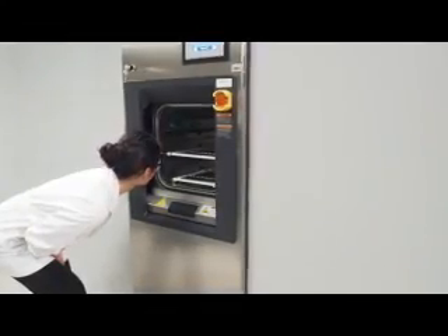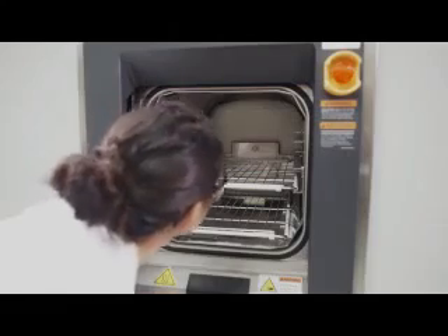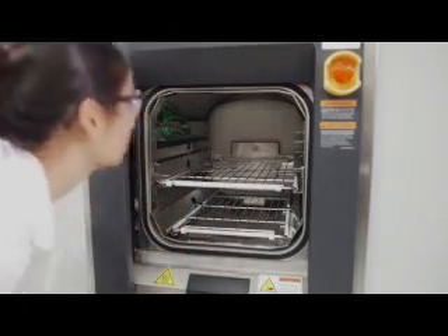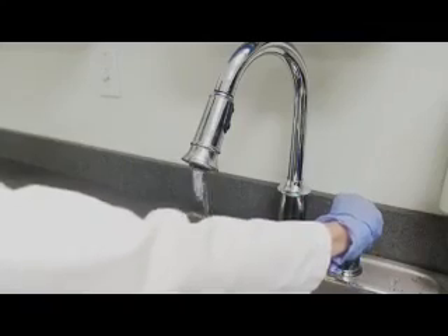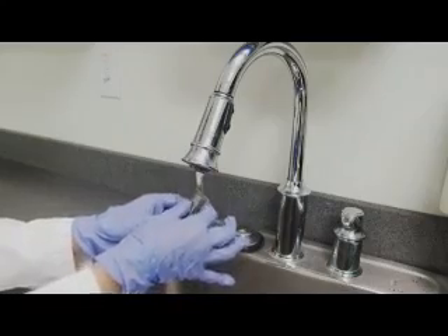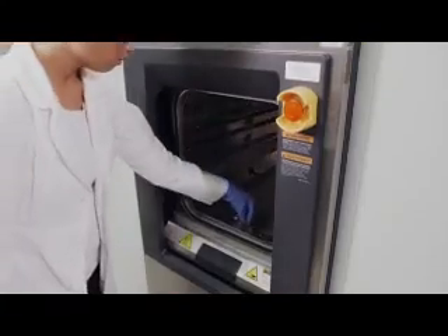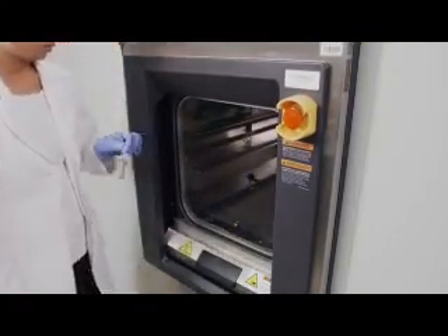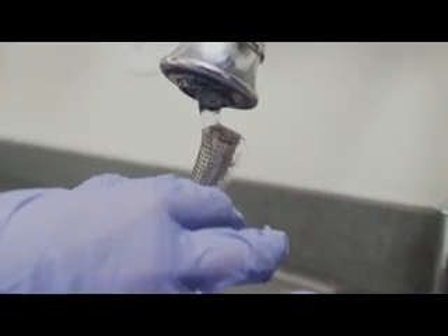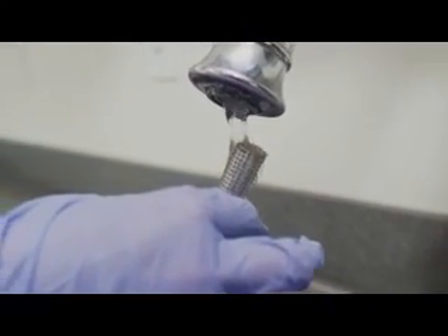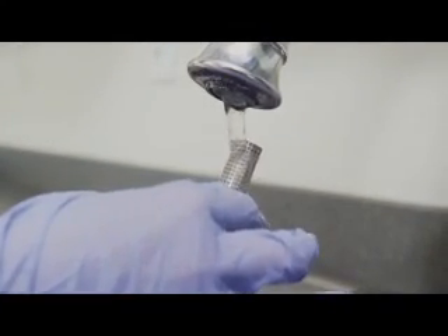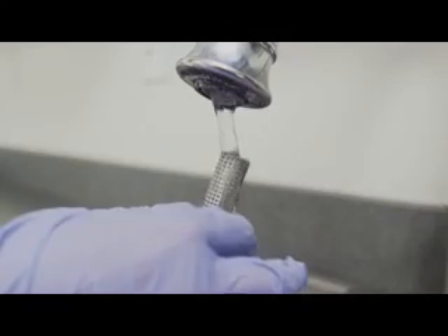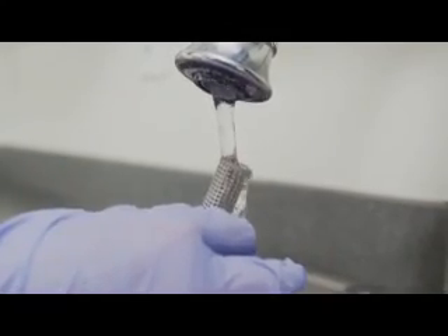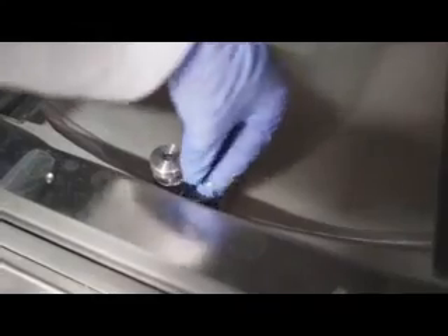STERIS recommends inspecting the interior chamber and chamber drain strainer each morning before running the daily warm-up cycle. Start by cleaning the chamber drain strainer when making an inspection of the chamber. After pulling out the drain strainer, remove any obvious debris, and if necessary, clear the screen in the strainer using a wire brush or similar tool. Once it has been cleared of obvious debris, reverse flush the strainer under running water. Replace the strainer in the chamber drain when complete.